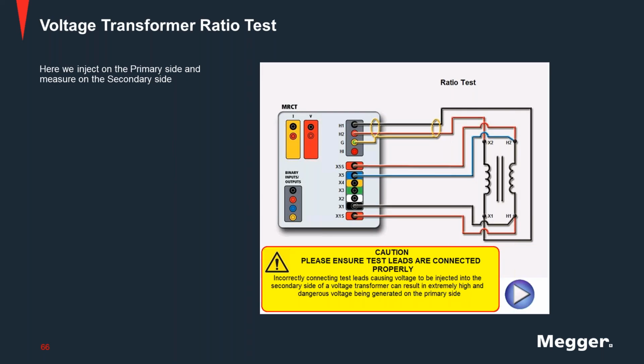So with our MRCT here, as you can see, because it is a voltage transformer, we must take extra care. We don't want to do a step up voltage here. Normally, when we do the ratio test for a voltage transformer, like the power transformer, we do the step down. So we inject on the primary side and we measure on the secondary side. This is what we are doing in the voltage transformer.